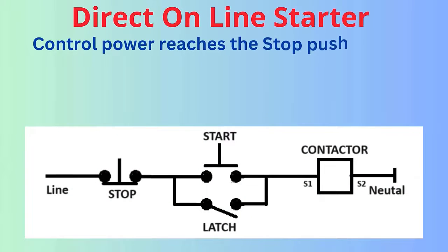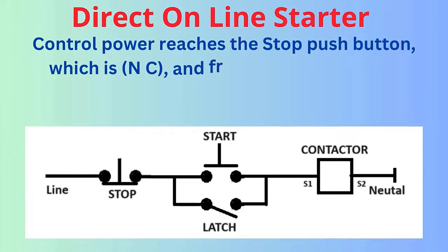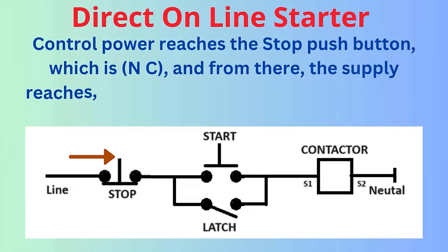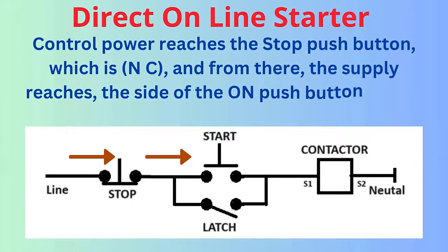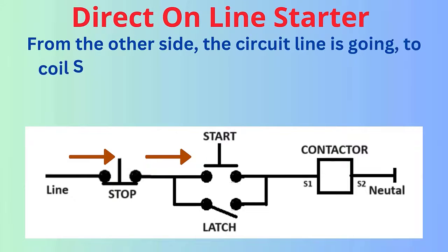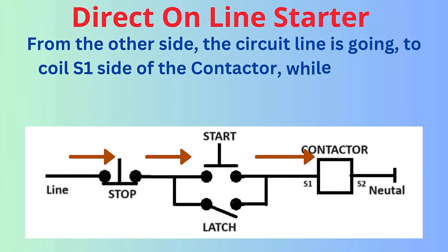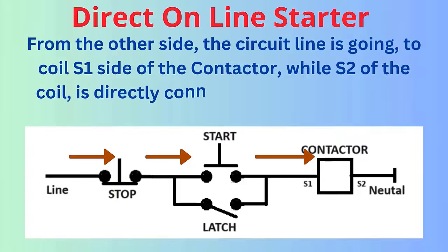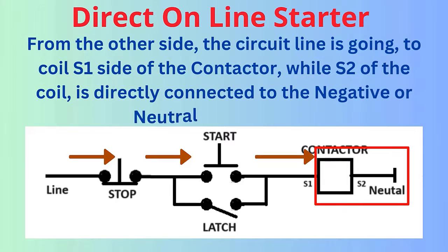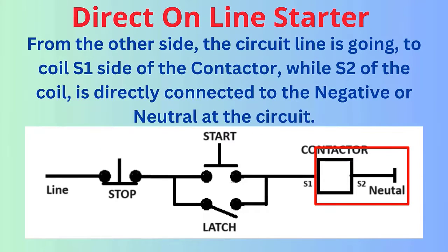Control power reaches the stop push button, which is NC, and from there, the supply reaches the side of the on push button, which is NO. From the other side, the circuit line is going to coil S1 side of the contactor, while S2 of the coil is directly connected to the negative or neutral of the circuit.